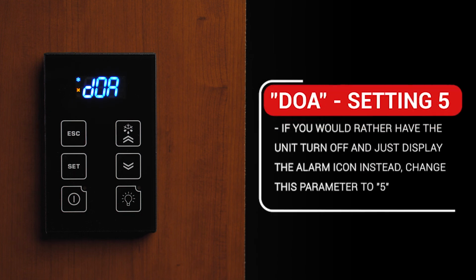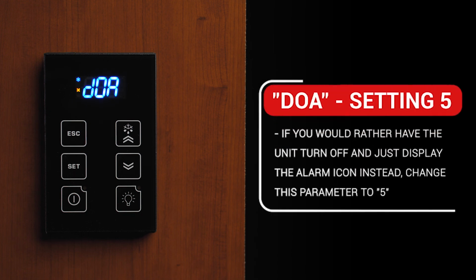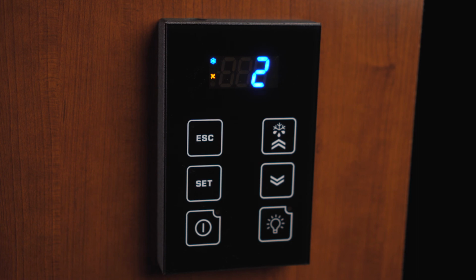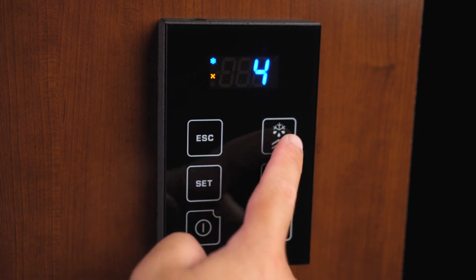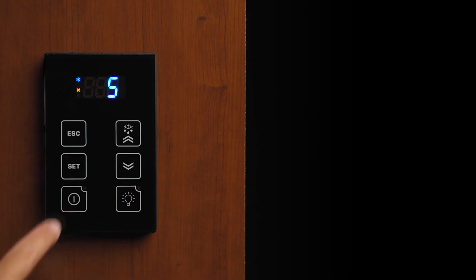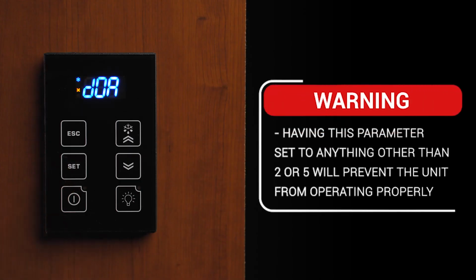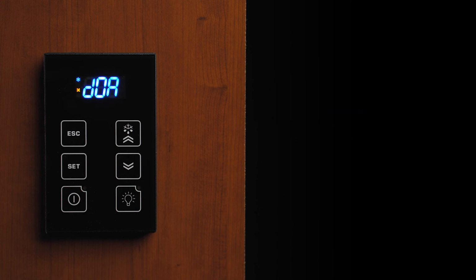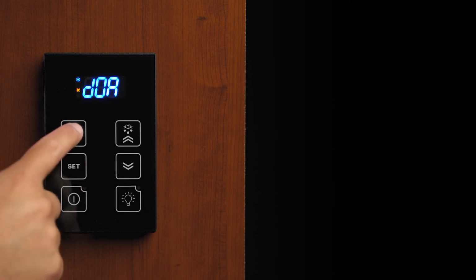If you would rather have the unit turn off and display the alarm icon, then you will need to press and release the Set button with DOA on the display, then use the up and down arrow to display 5 and press Set. Having that parameter set to anything other than 2 or 5 will prevent the unit from operating properly. We hope this video has been helpful in understanding the many functions of your KDT controller. Thank you for watching.